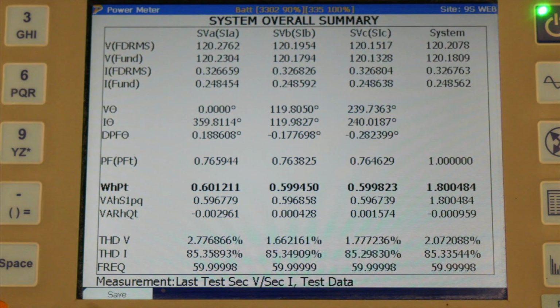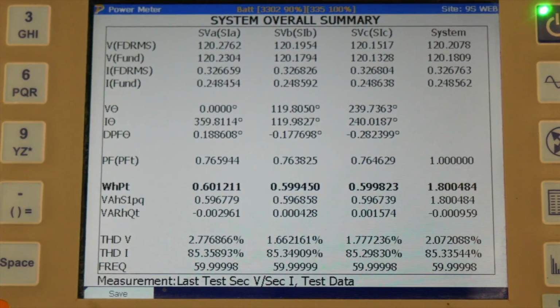That's a really good question, Chris. What you're seeing there is the difference between the fundamental energy, fundamental once again being 60 hertz, and the total energy. The top number, the IFDRMS, is incorporating all of the harmonics, including both the fundamental and the harmonic waveforms. The fundamental is only the 60 hertz component. So for this particular example, we're measuring about 250 milliamps on the fundamental and about 320 milliamps on the total system. That's a representation that there's a lot more harmonic energy. If we look down at the bottom, you notice the current THD is about 85%. So there's a lot of harmonic energy being put into that.